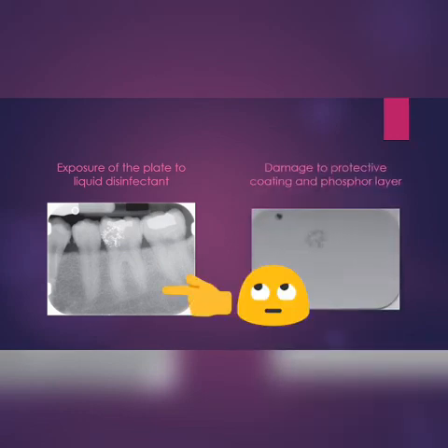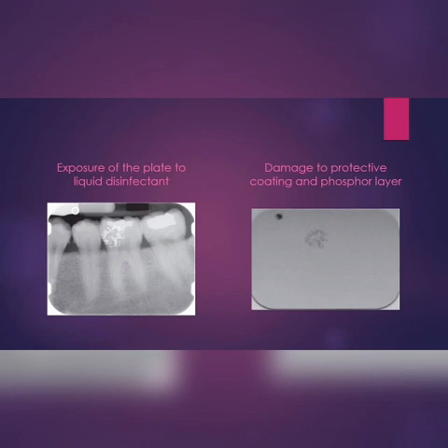The overexposure of the plate to liquid disinfectants can also produce artifacts that can compromise the diagnostic quality of the images, and there can be damage to the protective coating and the phosphor layer because of excessive use of liquid disinfectants as well.